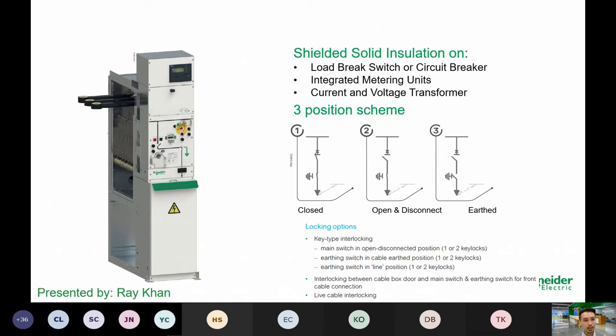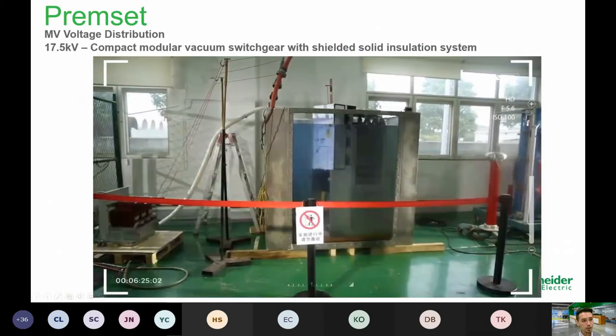Apart from this, they have other components like the load break switch or the circuit breaker used in the Premset. It has integrated metering units, with the CTs and VTs in place. This picture shows that they go through a very extreme test stage, to a point where they expect the Premset to be powered up and then submerged underwater. When the submersion takes place, you expect the Premset to be fully operational as well. What you can see here is a 17.5 kV test that has been issued on this unit.